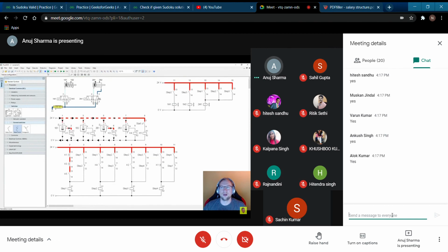So what we have now, if I press play, if I press the start button, you can see this switching over just nicely there. 1, 2, 3, 4, 1, 2, 3, 4. If I go to the single step here, I activated the start. Now K5 will activate. K5 will close this. That's the first thing that will happen. K5 here is closed. Activating step 1, right? Step 1 here will keep itself closed, even if K3 here is already open, which is a sensor, step 1 keeps itself active. Step 1 up here closes and activates 2M1.